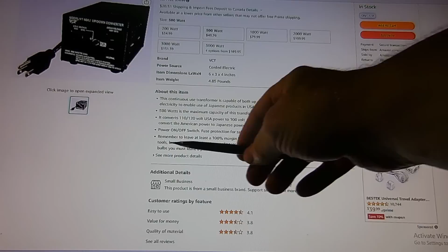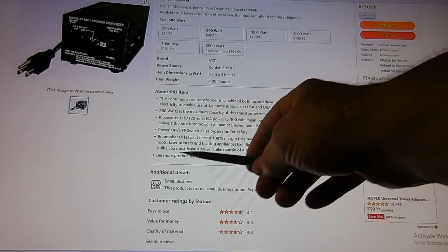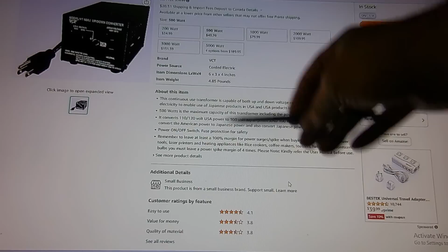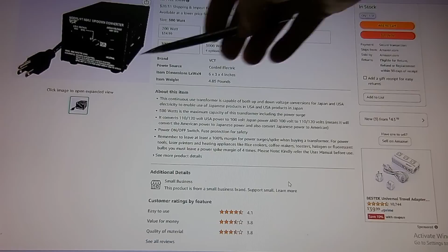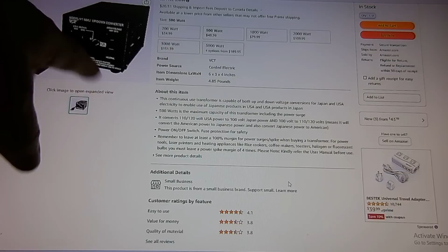It says to remember to leave at least 100% margin for power surges or spikes when buying a transformer. For power tools, laser printers, heating appliances like rice cookers and coffee makers, you must leave a power spike margin of 4 times. So what they're really saying is you can only use this for about 125 watts, even though it's rated for 500. The problem with these is if you put heavy loads on them for extended periods, they will overheat, and the thermal fuse will either blow out or they'll smoke.